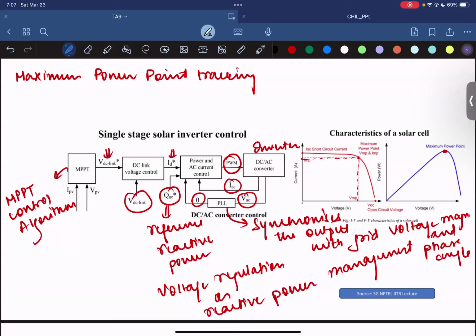When we checked the string voltage for inverters, there are conditions where it goes to 1090 also, but at that time the inverter is operating only, it is generating power also. Yes, if you are keeping your DC link voltage at a higher level than your inverter, it would generate power.